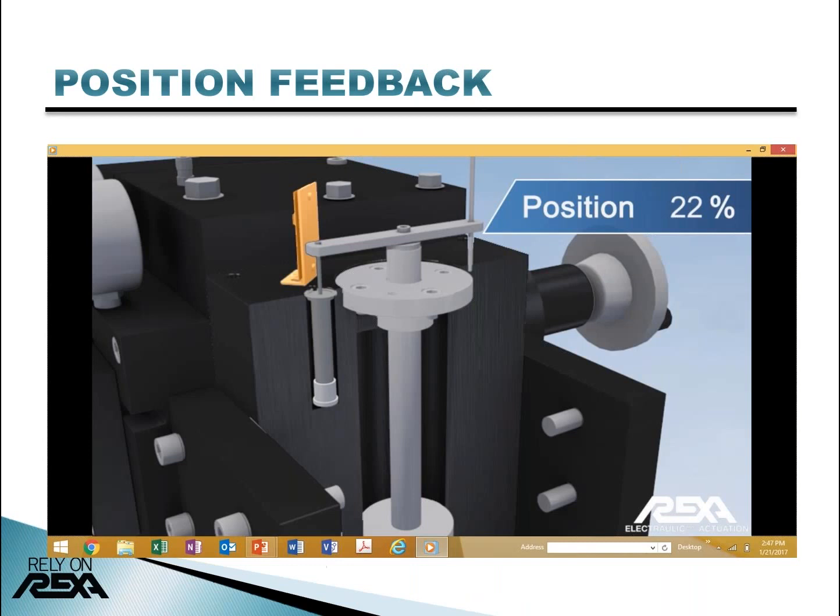The thin film potentiometer is directly coupled to the cylinder shaft. The cylinder type is rack and pinion gear, which delivers a constant torque throughout the movement range. The cylinder seals are rated for 2 million full strokes and 20 million dither cycles.